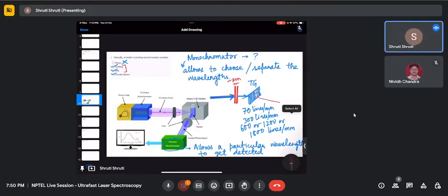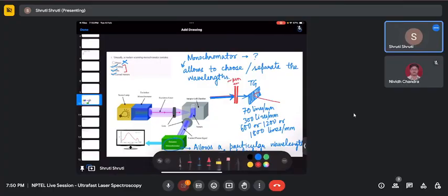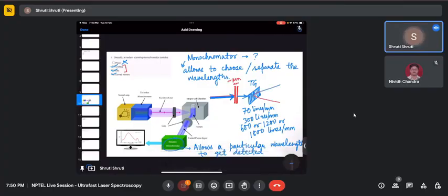But we never keep the spectrum, generally, I don't. It will not be a good idea to keep the slit width to the minimum so that the resolution will be maximum. Yes, the resolution will be maximum, but there will be very few photons. If the slit width is 1 nanometer, there will be very few photons, so the noise will increase. So you can keep slit width 1 nanometer only if your sample is highly emissive.